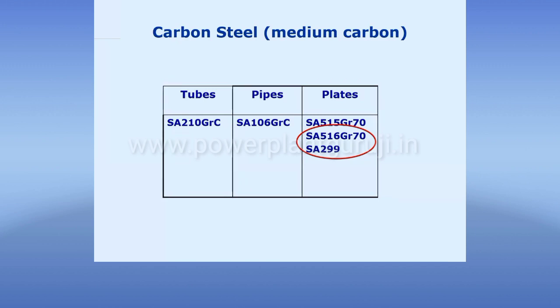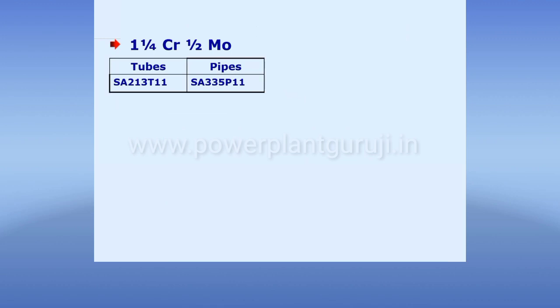The metallurgy we use there is chrome-moly metallurgy called T11 — SA213T11 for tubes and SA335P11 for the header. Note it down: this is having one and one-quarter chrome, that is 1.25% chrome, and half percent molybdenum.